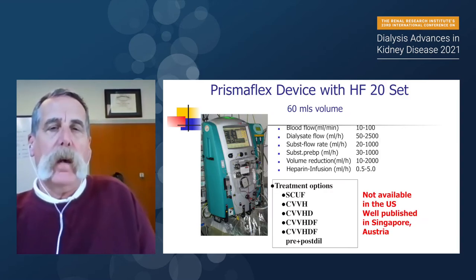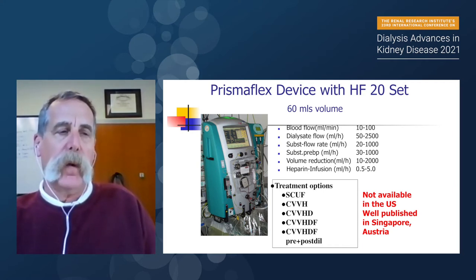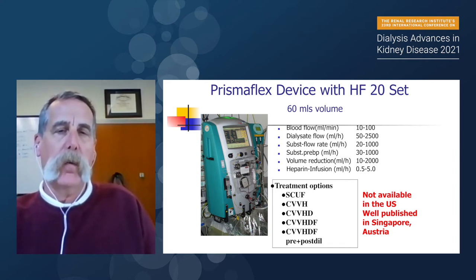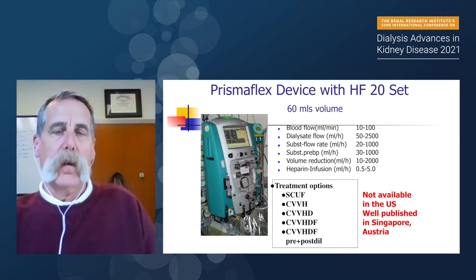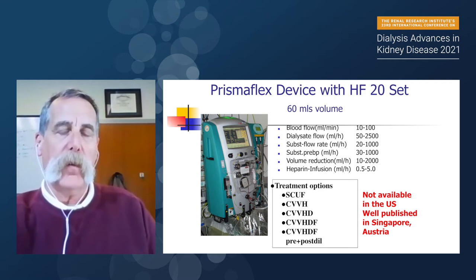In Europe and now in the United States under COVID restrictions, the Prisma Flex now has the HF20 set — a polysulfone membrane that allows for smaller children. For an 8-kilo child with intravascular blood volume of 80 cc/kg, that's 640 mL, putting you at about 9% extracorporeal, so a blood prime can be done. This has not been available in the United States until recently, but it's well published in Singapore, Austria, and a recent publication in Pediatric Nephrology from studies in North America.